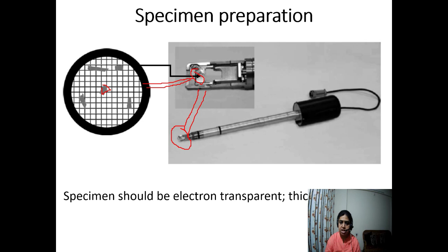Your sample should be electron transparent. That's why all samples cannot be analyzed in your TEM machine. Your sample should be electron transparent. This is very important. Now, thinning of the sample is a must. Suppose you have a sample which is not electron transparent, so we have to make it electron transparent.